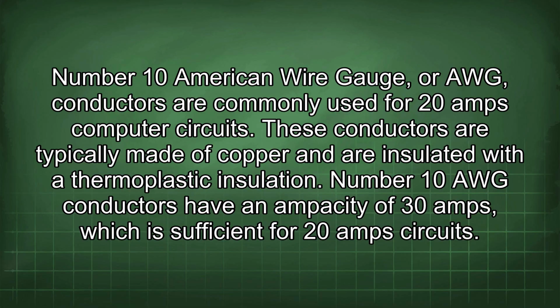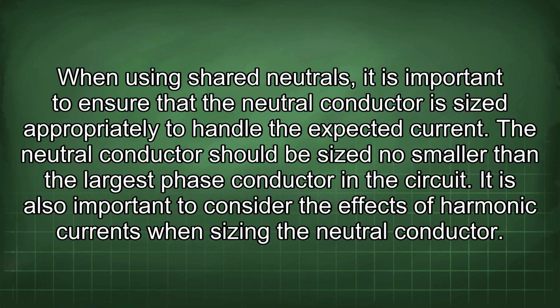These conductors are typically made of copper and are insulated with a thermoplastic insulation. Number 10 AWG conductors have an ampacity of 30 amps, which is sufficient for 20 amp circuits. When using shared neutrals, it is important to ensure that the neutral conductor is sized appropriately to handle the expected current. The neutral conductor should be sized no smaller than the largest phase conductor in the circuit.